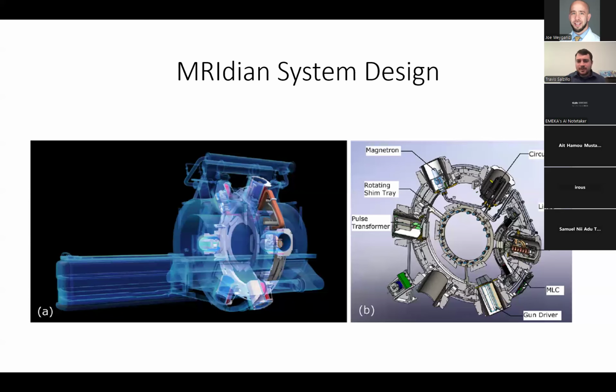This is a system design. It uses a magnetron as its power amplification for the acceleration of the electrons. It has a linear accelerator output here, and that is orthogonal to the high field magnetic field that runs in the transverse direction. All the other systems are pretty typical of what you'd find in these linear accelerator-based systems, like a circulator. You have your MLCs, you have your electron gun, and so on and so forth.